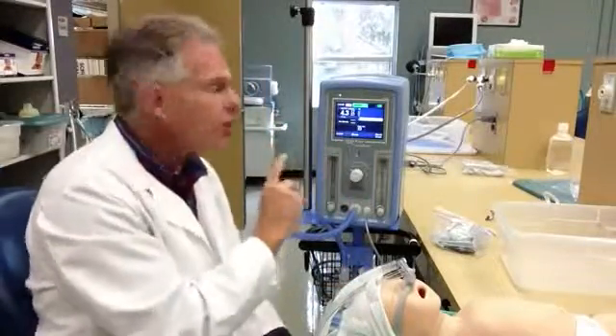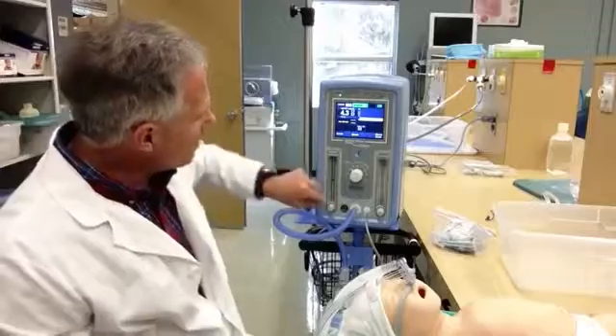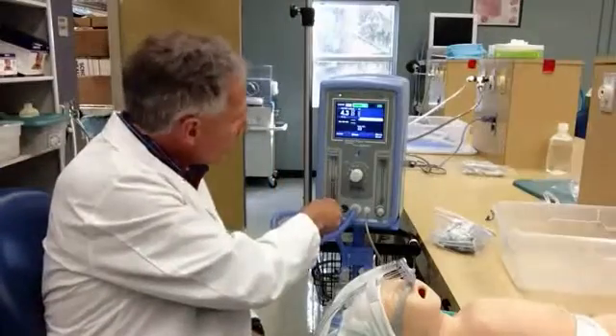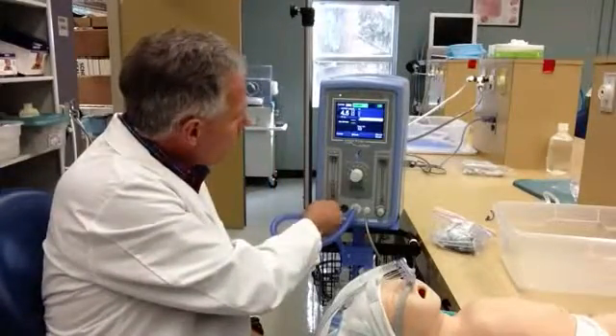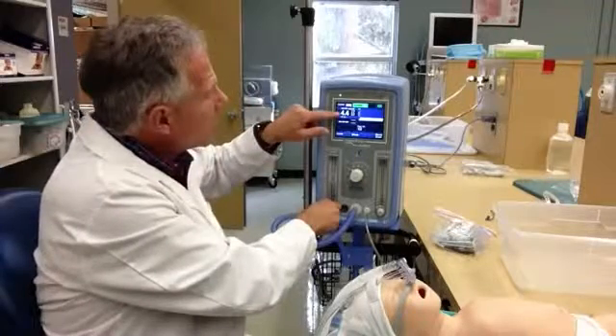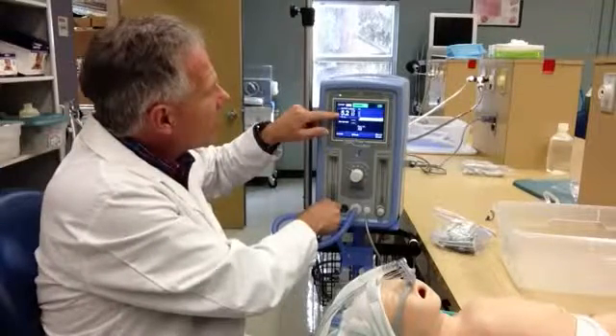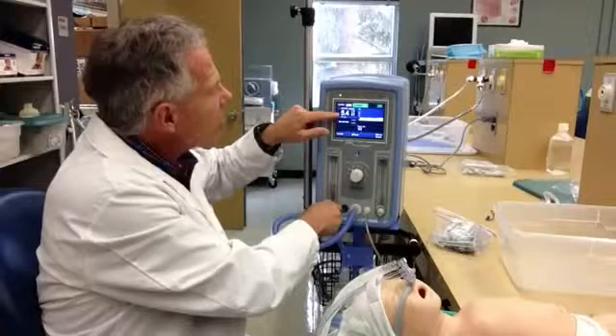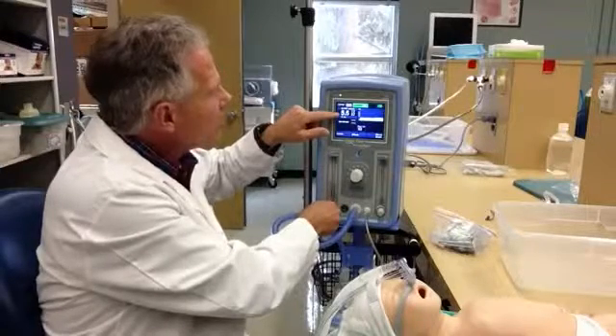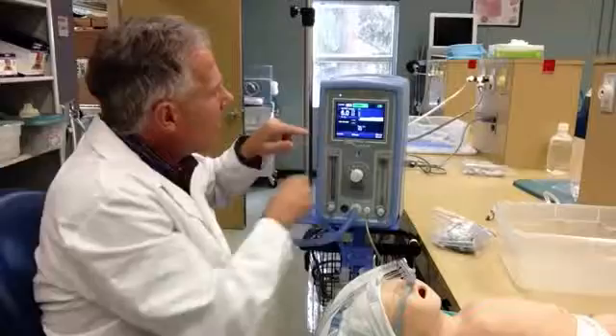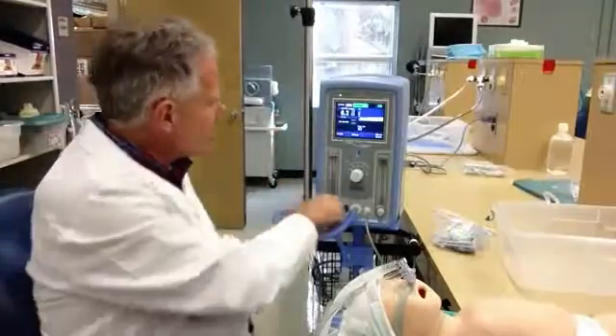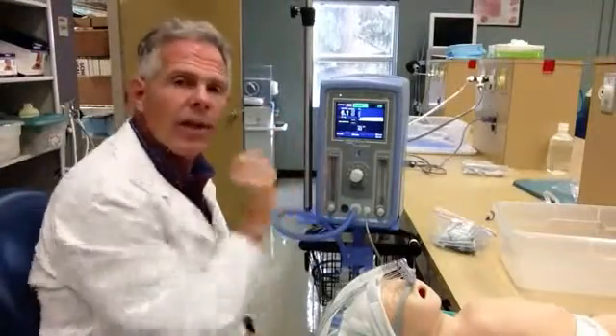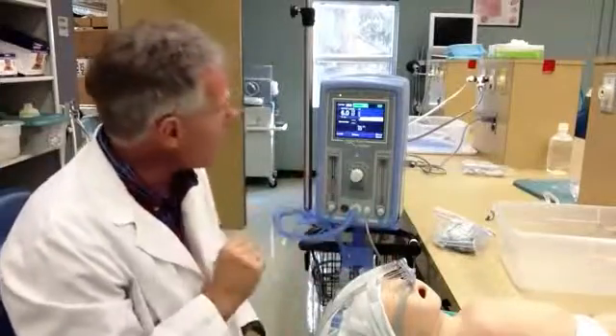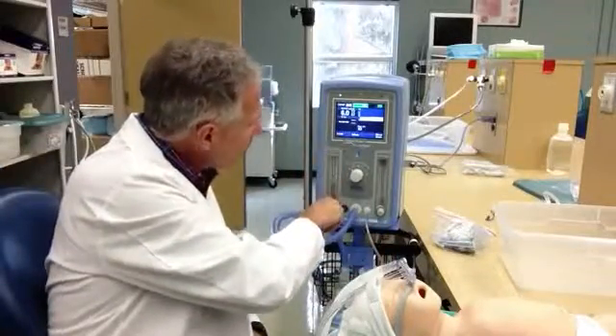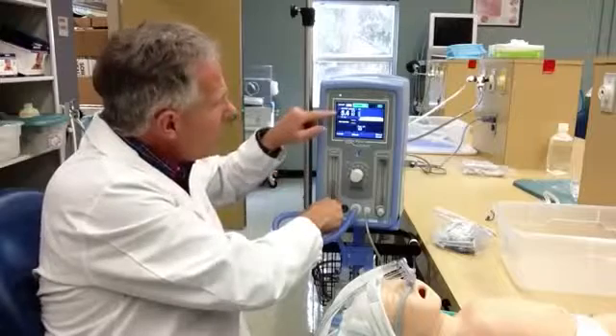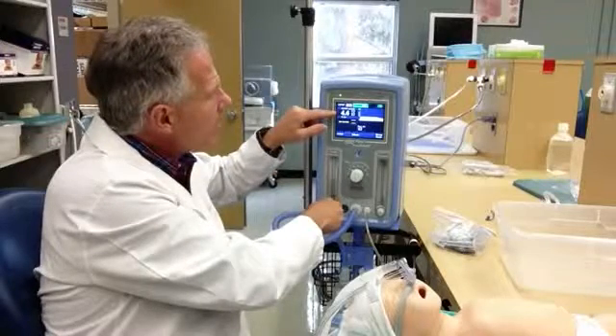Now I'm going to fine-tune my level of CPAP with my flow. All right? So by increasing the flow, I can bring up my CPAP pressures to what I want to have delivered for my patient. In this case, we're going to target 5. Oh, maybe we should go up to 6. All right? So I can target my CPAP pressure by adjusting the flow, and that's one of the key elements of the SiPAP device. If I only wanted 4 centimeters of water pressure, I'm going to cut down the flow until I just see a nasal CPAP pressure of 4.